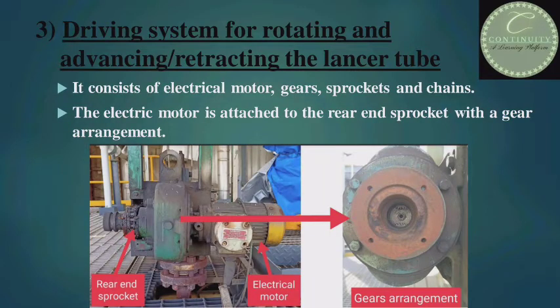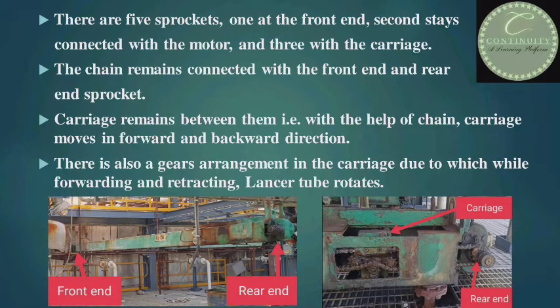Third part: driving system. It consists of an electrical motor, gears, sprockets and chains. The electric motor is attached to the rear end sprocket with a gear arrangement. Look at the figure — there are rear end sprocket, gearbox and electrical motor. There are 5 sprockets: one at the front end, one connected with the motor, and three with the carriage. The chain remains connected with the front end and rear end sprocket. With the help of the chain, the carriage moves in forward and backward direction. There is also a gear arrangement in the carriage, due to which while forwarding and retracting, the lancer tube rotates. The figure on the left side shows the front end and rear end of the soot blower, and the figure on the right side shows the carriage.